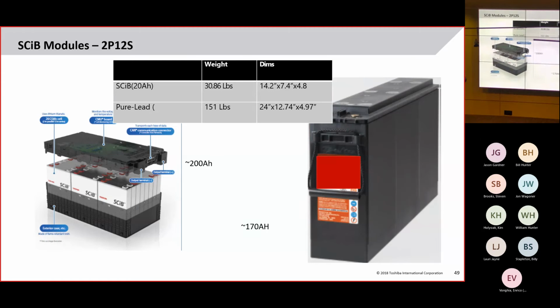When you compare a VRLA jar to lithium-ion in general, you'll see about a 1/5 weight differential - in this case 150 versus 31 pounds. That's a big difference. Once you factor in the entire solution, the differential isn't 1/5 but more like 1/3 - still substantial. If you're doing replacements, the reduced weight helps, but you get more advantage doing a new build, because your concrete requirements change. Instead of needing to support 50,000 pounds, it's more like 17,000 pounds. The specs vary a lot, and there's a lot of savings to be had.